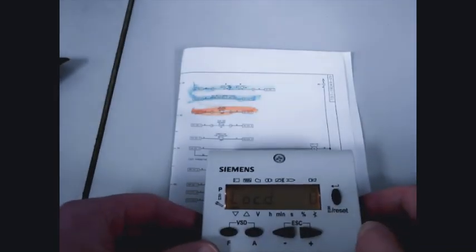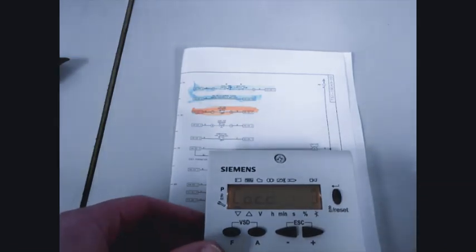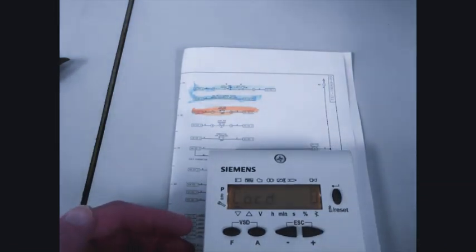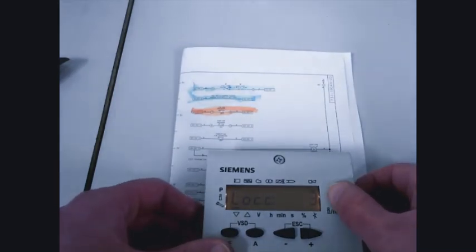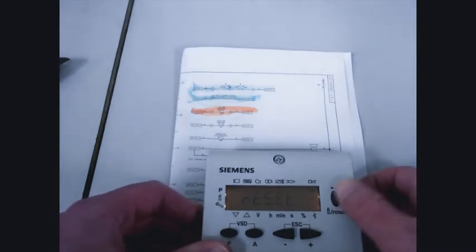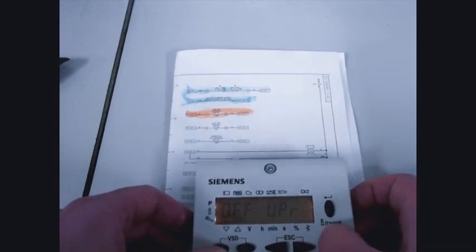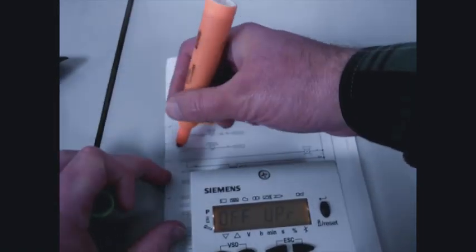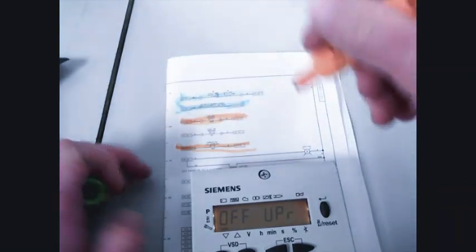We get an error code 3, diagnostic 0. Turn the burner switch off and reset the error. Correct any issues with the combustion air switch so that when the blower motor is on, we have power to X302.1.